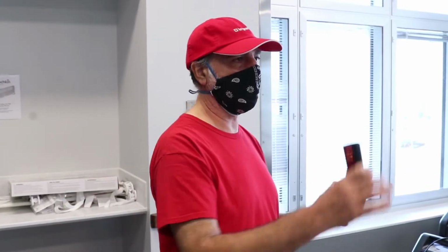So anybody passing through or sound will just keep the timer starting back to 20 minutes and counting down, and it'll go back to 20 and count down again. So that's how it knows when there's absolutely no infrared motion, no ultrasonic detection, then the lights will turn off after 20 minutes.